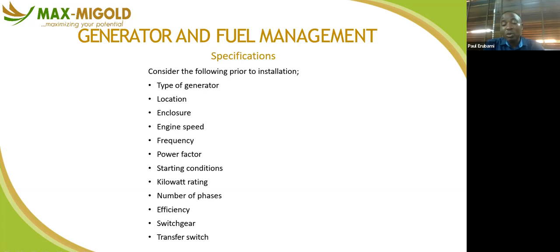If your changeover is too low for the rating you have, maybe you bought a 100 kVA generator and you want to buy a 63 amp changeover, before you know it, in less than a month, the terminals of your changeover will start wearing and burning out. Before you know it, you start having partial contact. It will affect your generator and the appliances that you are using it for. So it's better you size right when you are procuring your generator. If you don't know how to do it, engage a professional. Because you feel you are saving by not engaging a professional, we end up spending two times, if not ten times, what you were supposed to spend.